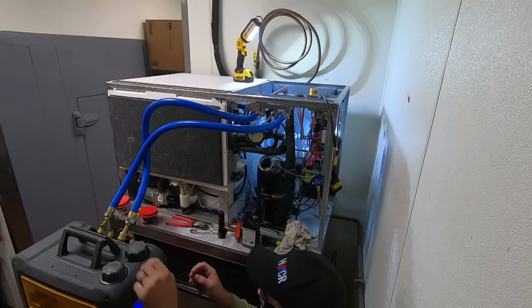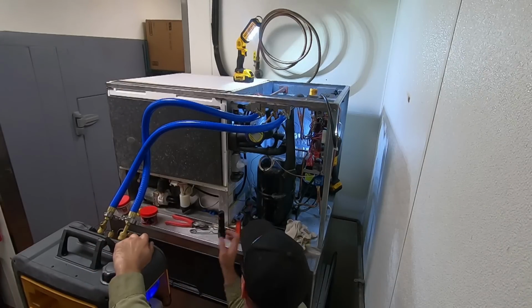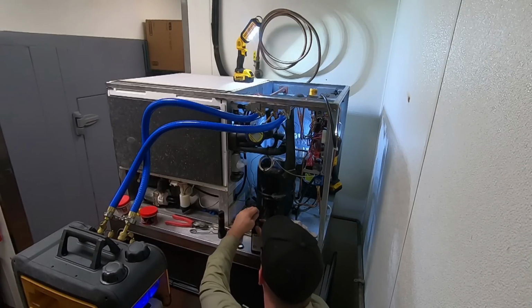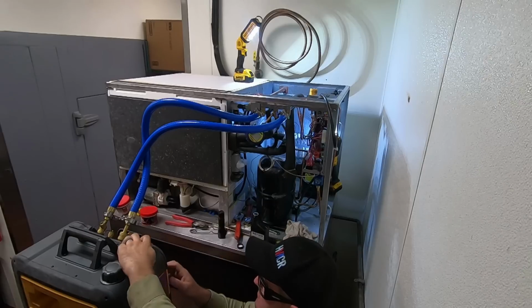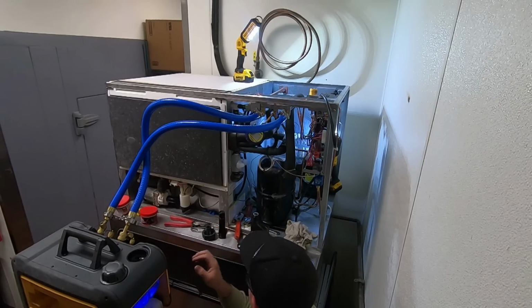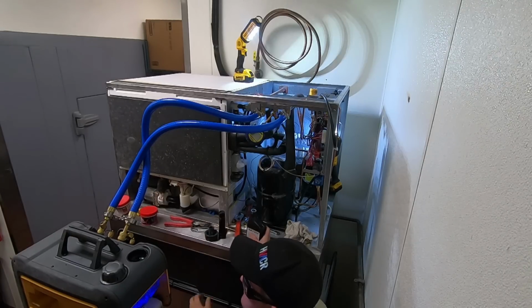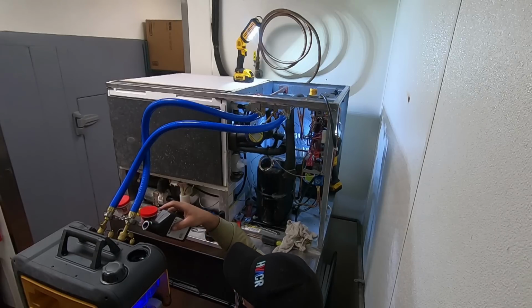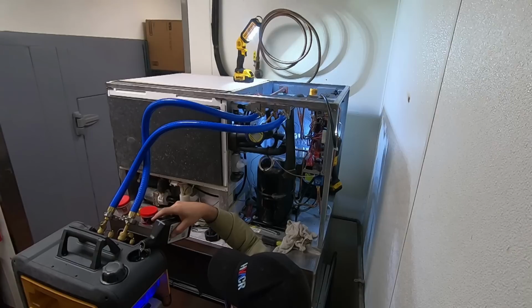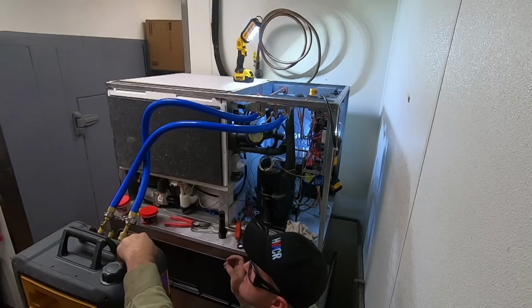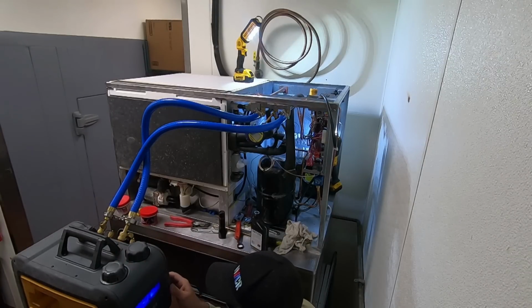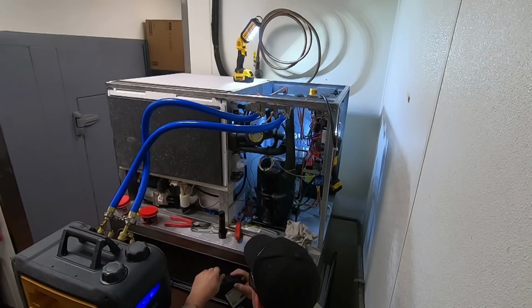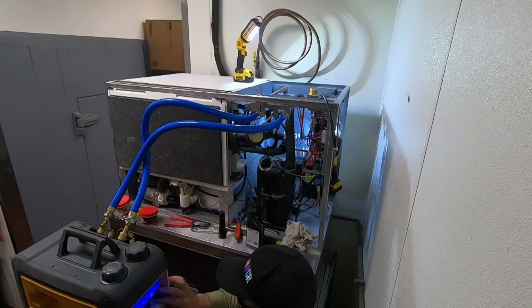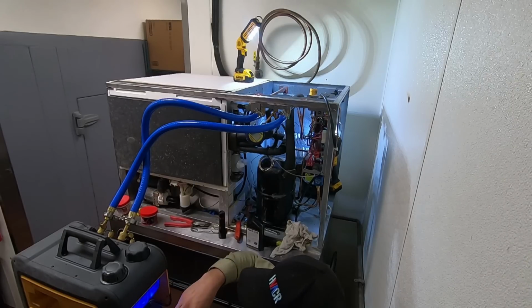I really like the feature on the Fieldpiece VP85, and there's a similar feature on the Appion Tez 8, where you can do the on-the-fly oil change. In my situation, I started my evacuation, let it pull down to about 2,000 or 1,000 microns, and because I could tell the oil was getting cloudy, I went ahead and did an on-the-fly oil change so I could get a much deeper vacuum. One of the things on the VP85 vacuum pump is you also have the gas ballast. So even before I got down to about 2,000 microns, I had the gas ballast open. Then I closed it, got it down to 1,000 microns, and changed the oil. Anyways, I really like that feature on this pump, and I have no affiliation with Fieldpiece other than occasionally testing products for them, so take it for what it is.